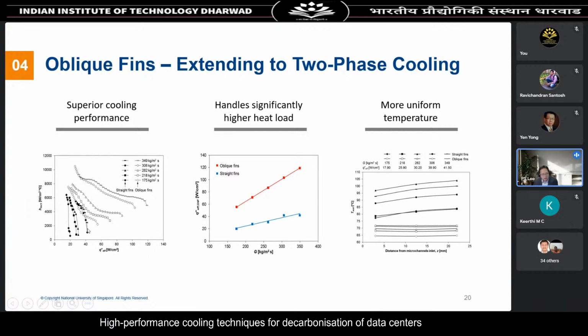So the implication is that we're able to extend the working range for two-phase cooling once we deploy oblique sectional fins. We've also captured the critical heat flux, shown in the middle figure. Comparing oblique sectional fins versus continuous straight fins, the oblique sectional fins achieve a critical heat flux easily 3 times that of the straight fins, again attesting to the effectiveness of this technique when extended to two-phase cooling.